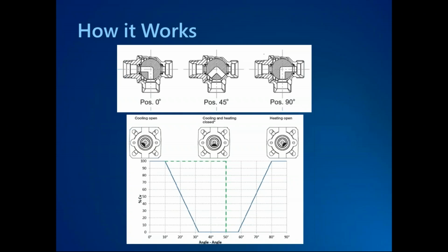So the number of steps, the number of increments when it comes to doing this modulating, is not as good as you potentially see with a traditional 2-way control valve that would be sized for the designed pressure drop. But we have some ways to address that. We'll look at moving forward. But you have this modulating control going from effectively 0 degrees down to about 30-degree rotation, at which point you're going to hit a dead band where you have full isolation for both heating and cooling. And then as the 6-way rotates the remaining 30 degrees, you are going to be modulating up on your heating control.